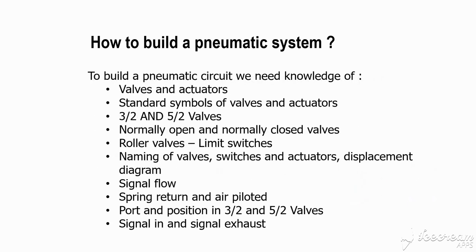How to build a pneumatic system? Before building a pneumatic system, you need to understand valves, actuators, and their standard symbols. You should also know what 3x2 and 5x2 valves mean. A 3x2 valve means 3 ports and 2 positions; a 5x2 valve means 5 ports and 2 positions. These are used for directional control valves or switches in pneumatic systems.